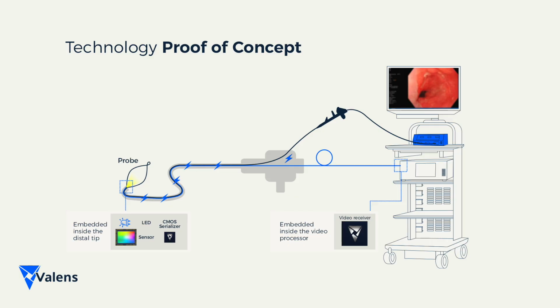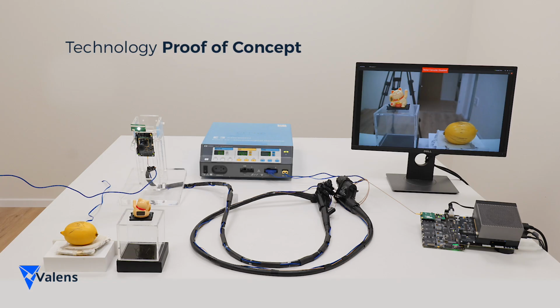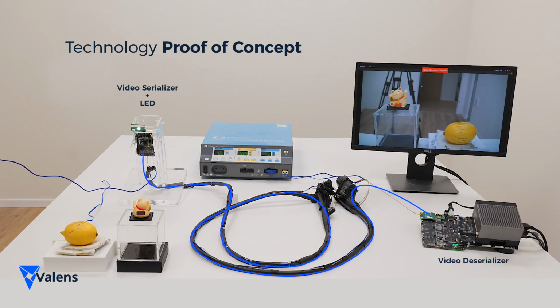probe for cauterization. At the tip of the scope, we have a 4K CMOS sensor running at the highest frame rate. The sensor data is driven from the tip of the scope using the Valens VA7031 serializer over a very thin and flexible 5-meter coax cable. On the receiving end, the Valens VA7044 deserializer is connected to the NVIDIA Orin processor that displays the 4K video.